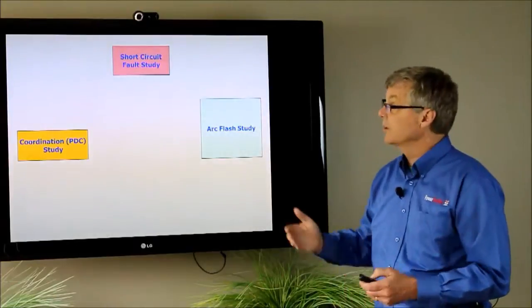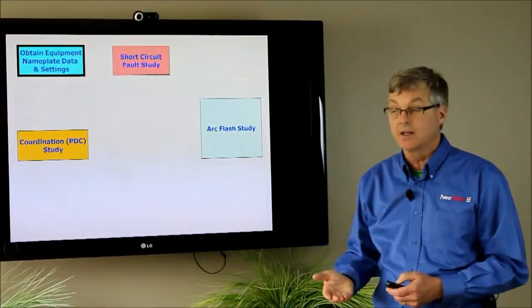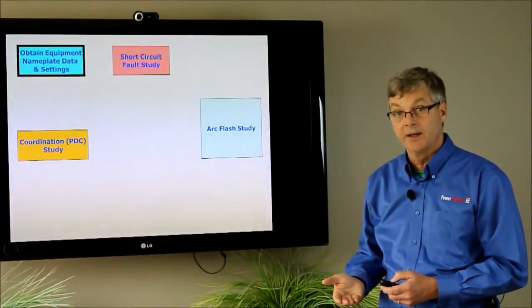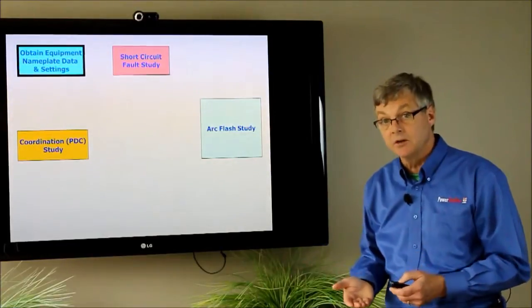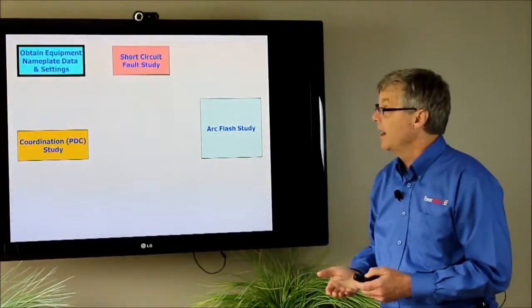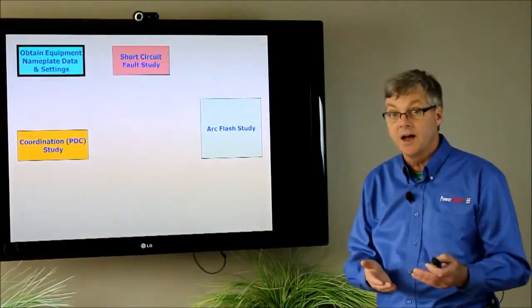So before we can do either one of these studies we need to go to the site and collect all the existing equipment nameplate data and that's a very time-consuming detailed process and it takes quite a bit of time to do and it sometimes is 50 to 60 percent of the cost of doing an arc flash study.